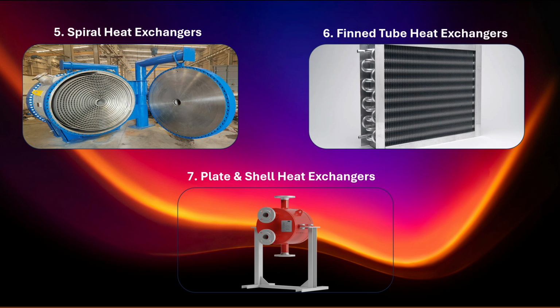It combines plate and shell designs, offering high heat transfer rates, high pressure and temperature resistance, compact size, and low fouling advantage. The type of heat exchanger is selected based on process requirements such as fluid type, temperature, pressure, space availability, and fouling tendencies.